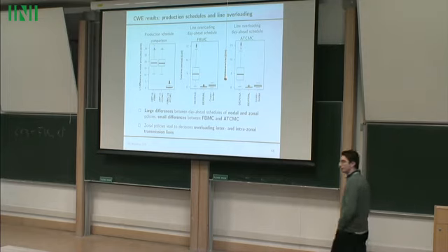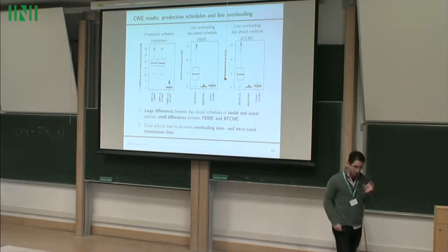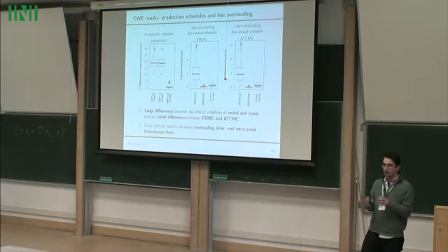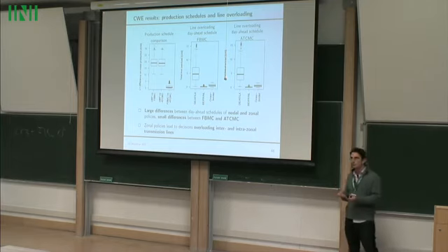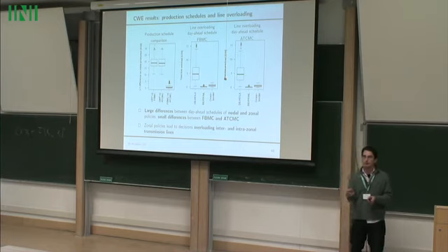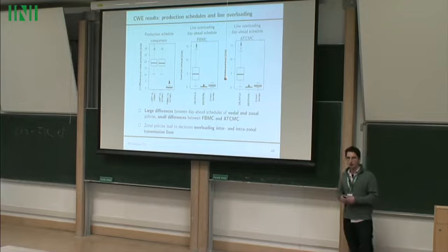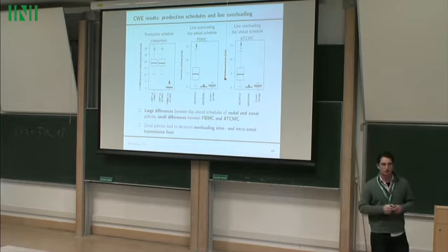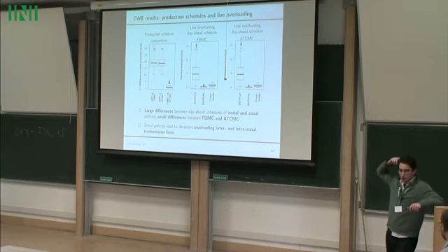So we're sticking to feasibility, sticking to the commission law. The only thing we're requiring is the legal statements, and then we're trying to find a projection in the zonal injections. You could argue that you can't do better than that, because if you step out of that polytope, you're illegal in one way or another. Implicitly that's how we're doing it. That's why you also saw that we're more accurately capturing the flows on the congested lines and overloading lines less.